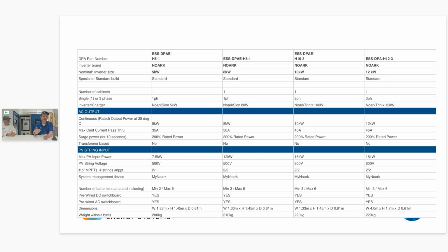That's the big difference between managed and unmanaged batteries. With unmanaged batteries, you have to have conservative values for voltage and current to fit all scenarios, so the maximum charge current has to apply across the whole charge range and all temperature ranges. Whereas when it's managed, you can change those values, so you can charge and discharge it more in the middle than you might at the top or bottom. It can dynamically control those based on cell voltages and temperatures.